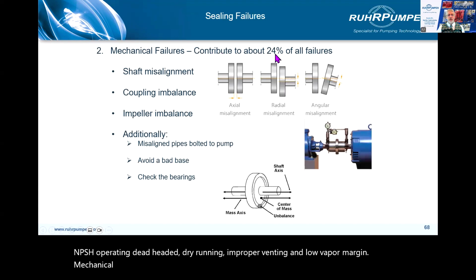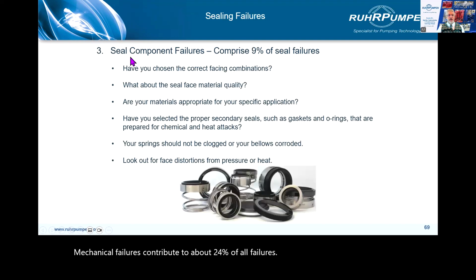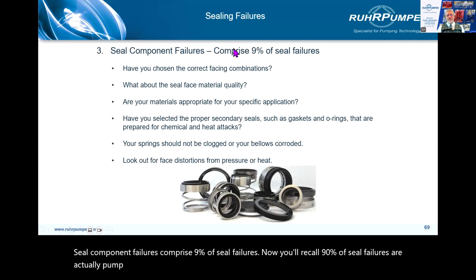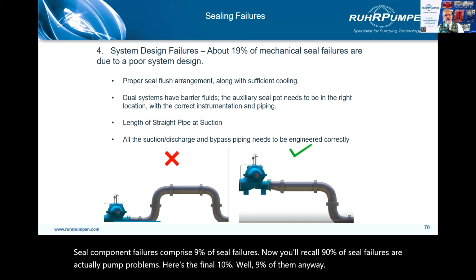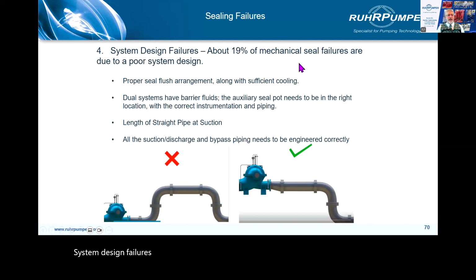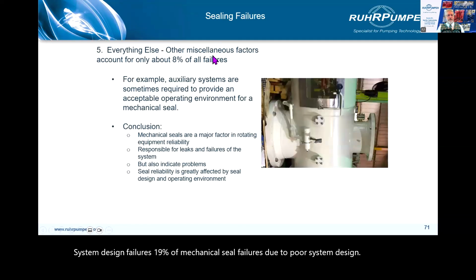Mechanical failures contribute to about 24% of all failures. Seal component failures comprise 9% of seal failures. Now, you'll recall 90% of seal failures are actually pump problems. Here's the final 10%. Well, 9% of them anyway. System design failures. 19% of mechanical seal failures are due to poor system design. And everything else, 8%.